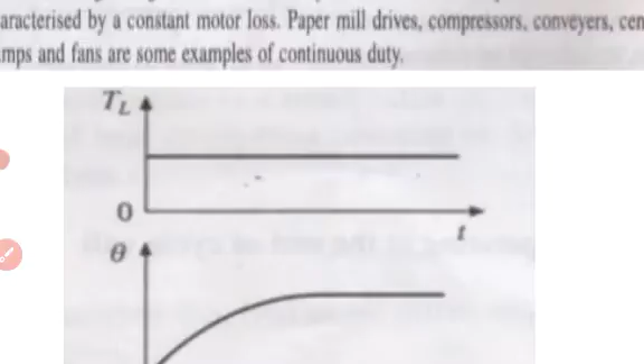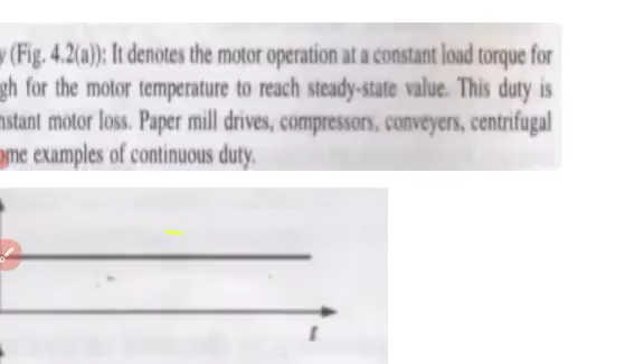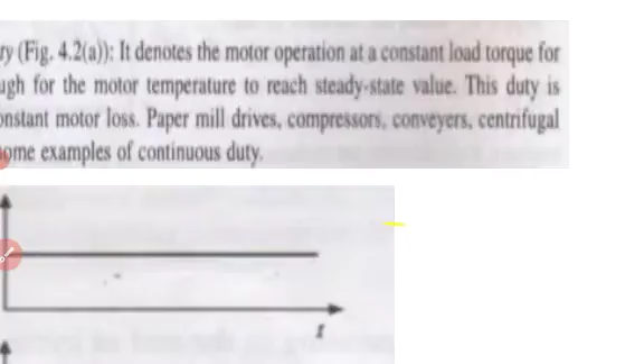First one is continuous duty. Continuous duty means the load is there continuously. It denotes the motor operating at a constant load torque. If you look at this graph, the load is constant, for a duration long enough for the motor temperature to reach steady state value. This duty is characterized by a constant motor loss. Paper mill drives, compressors, conveyors, centrifugal pumps and fans are some examples of continuous duty.